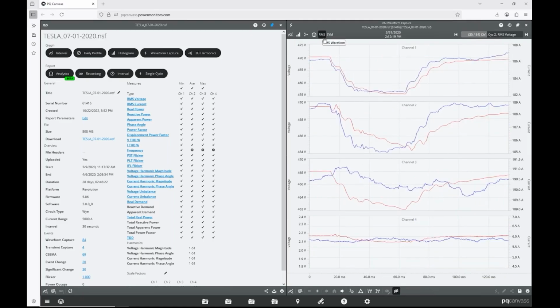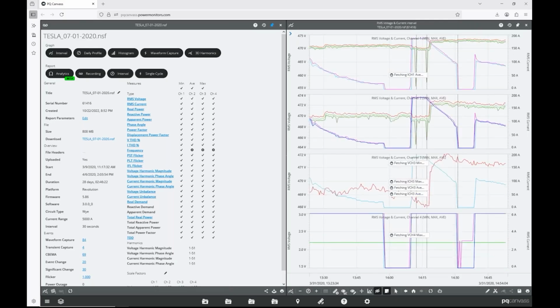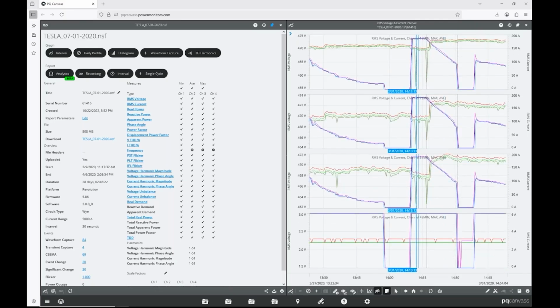Now, if we look at the RMS capture here, we can see that it's a deep voltage sag. We're dropping about 25 volts on a 480-volt system for about 3 cycles. But that didn't really affect the chargers at all. These charging systems are usually pretty insensitive to voltage sags. They're most sensitive to absolute voltage and voltage imbalance rather than voltage sags.